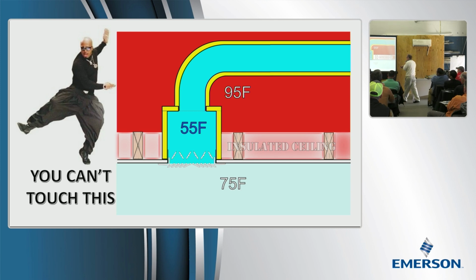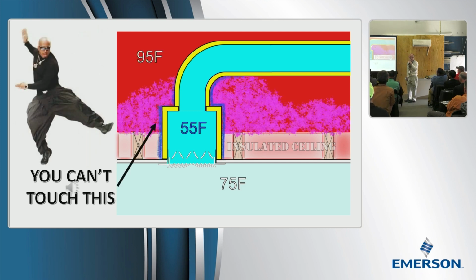Yeah, as a matter of fact, I'm going to say don't touch this. That's what I'll say, because what I measure is the dew point in the attic might be 75 degrees, but I stick that psychrometer down in this fluffy stuff, and we're going to talk about why that is. Moisture molecules, they love surfaces, they don't want to be in the air. Did you see Mr. Bergman's thing this morning about desorption? We're going to get into that because it's the same thing, just happening inside copper tubing. What we're doing is the same thing, but it's on the outside of a duct.